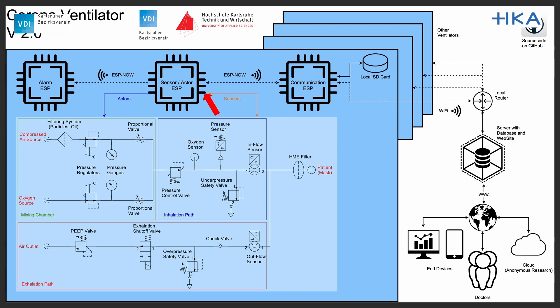Next, the pressure control loop. The pressure after the mixing chamber is still too high for artificial respiration. In addition, ventilation should not only be an opening and closing of the air supply — it should rather be a closed-loop control procedure. This requires an additional proportional valve as well as a relative pressure sensor. The control loop is calculated on the sensor/actor ESP, which, depending on the resulting pressure in the system, controls the inhalation airflow with the proportional valve.